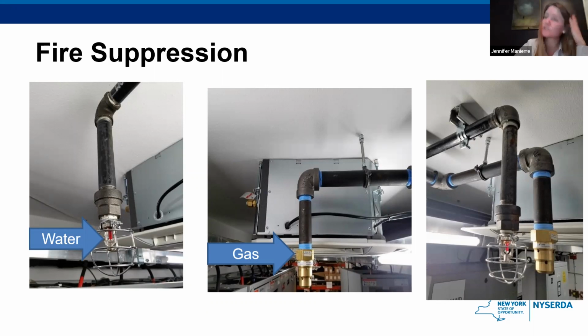Folks often, I've encountered this many times in doing this training, are afraid to associate water with lithium-ion batteries because they've heard that water reacts with lithium in a very bad way. That is true for lithium metal, but for lithium ion, you do not get that same reaction. Water is actually going to be one of the best ways to put out a fire for lithium-ion batteries. It will render the batteries completely useless going forward, but I think the fire was going to do that anyway. So water is a really great way to deal with lithium-ion fires. Not just because it will put it out right away, but because it's going to cool the battery down enough so that there's less of a chance of it reheating and reigniting after the fire has gone out. It puts it out and cools it down to prevent any reignition.